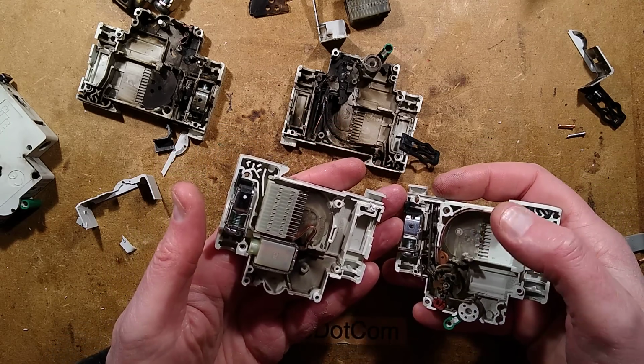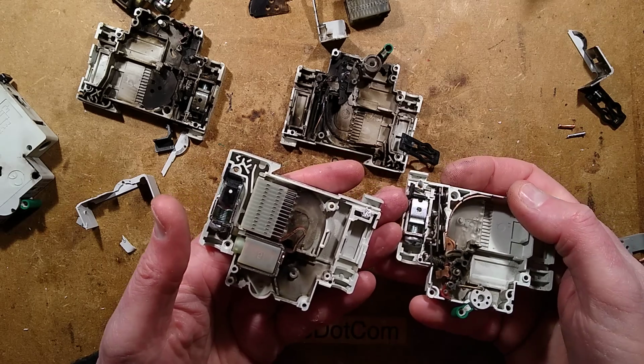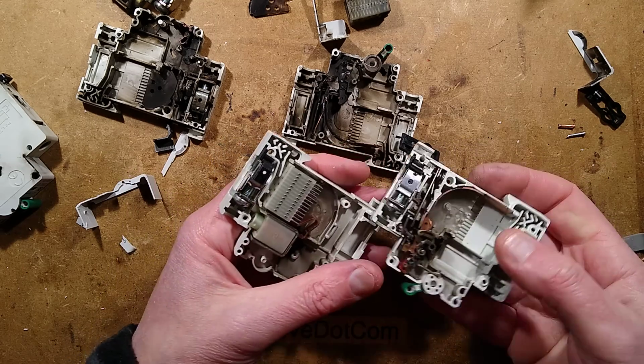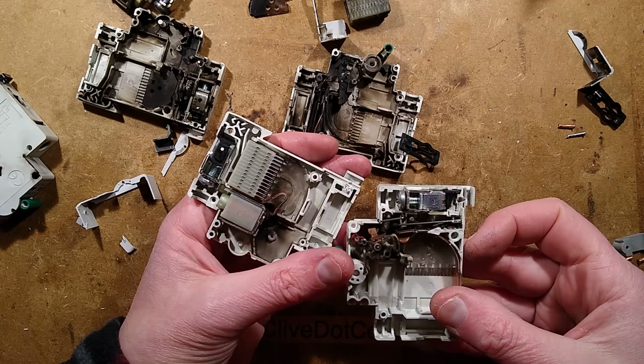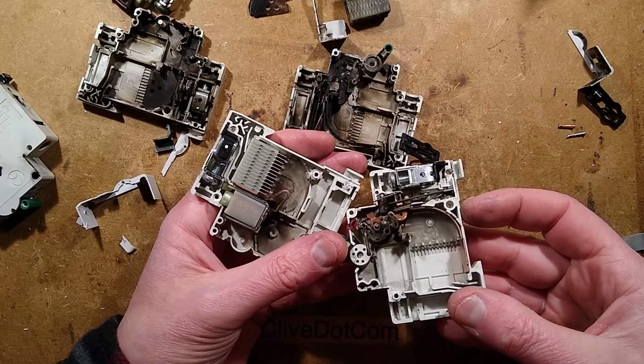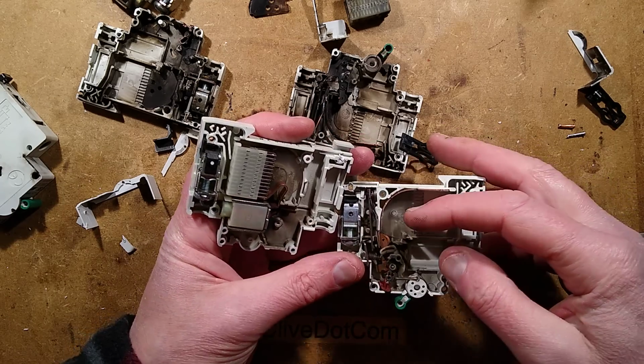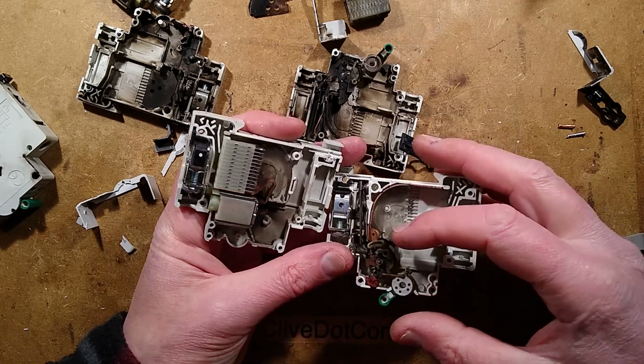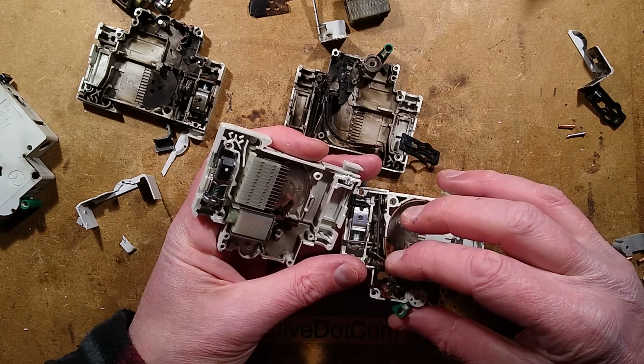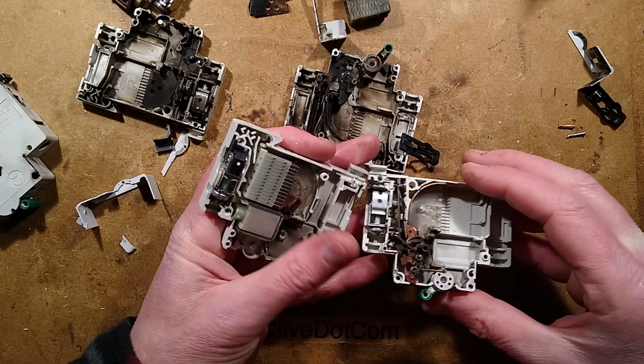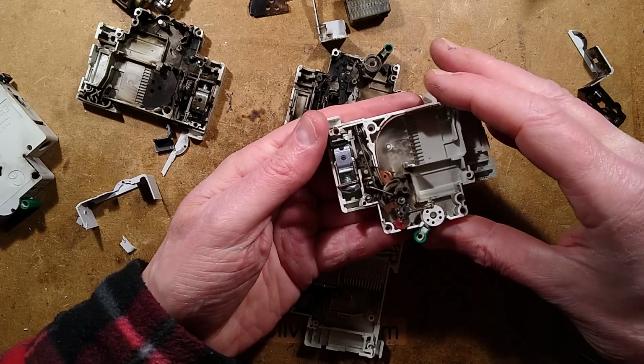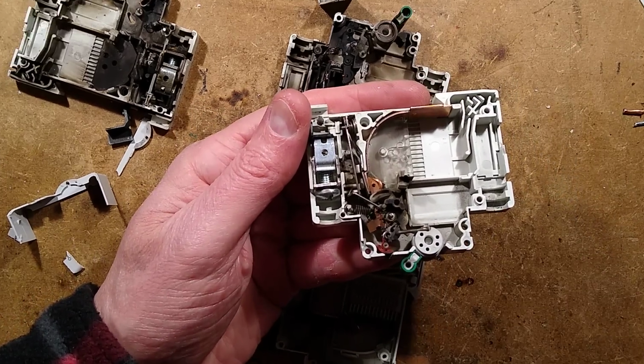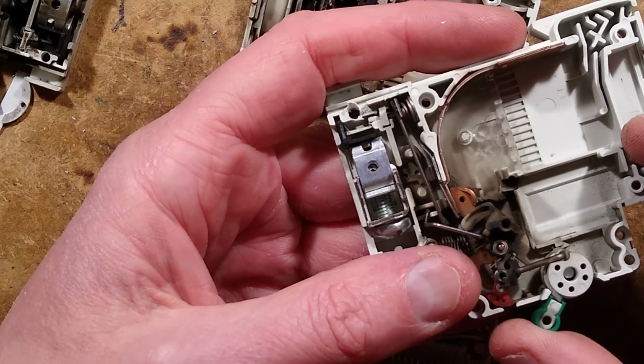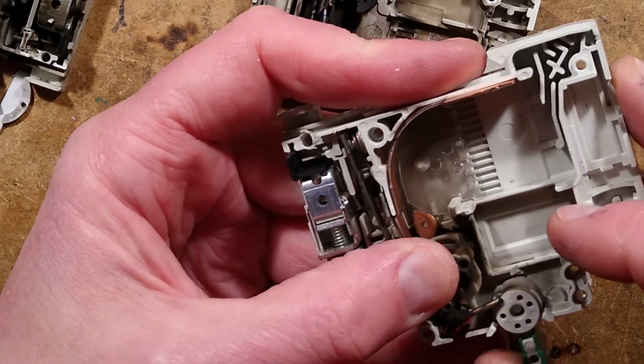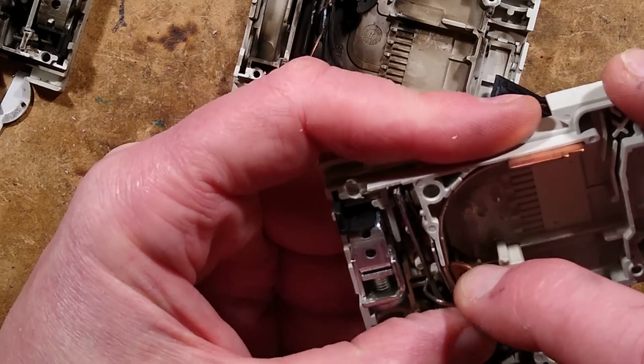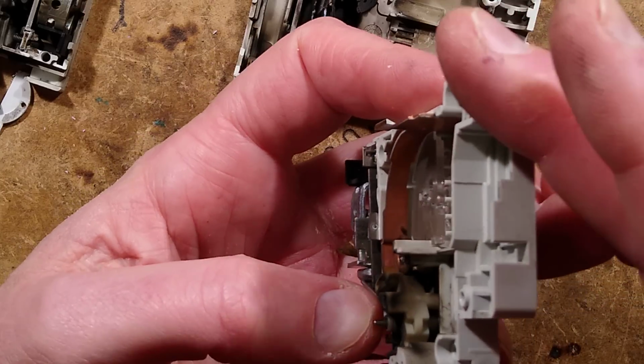So this is going out to one side of the arc chute. Where's the actual contact? I'd normally expect the contact to be swiping inside here. Oh, there it is. So there's the contact. If we zoom down this, by the look of it, yeah, there's the contact there. It's kind of like a knife contact, which is quite unusual.